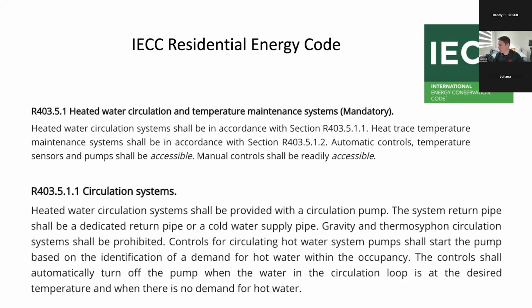Before we jump into that, we have one question that came in the Q&A, back to what you said earlier about the pump running dry and having cavitation. Is there a procedure or how do you recover if the pump shuts off due to air in the lines? That's a great question. And I have a slide that's coming up that's going to show you exactly how a proper return line needs to be configured in order to bleed the air out of the line. I'm going to get to that in just a few slides.